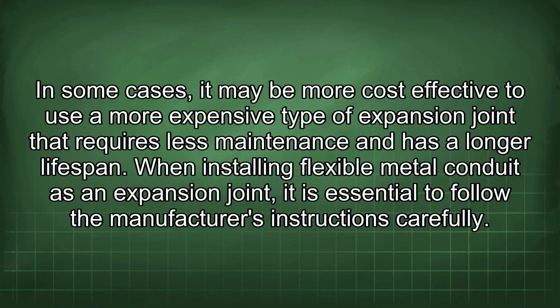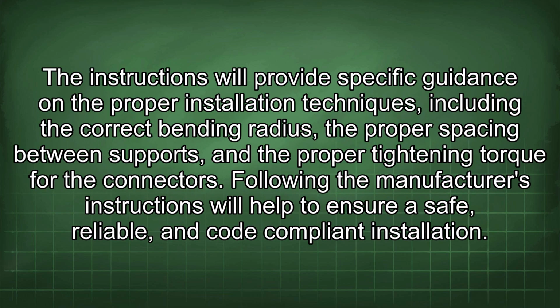When installing flexible metal conduit as an expansion joint, it is essential to follow the manufacturer's instructions carefully. The instructions will provide specific guidance on the proper installation techniques, including the correct bending radius, the proper spacing between supports, and the proper tightening torque for the connectors. Following the manufacturer's instructions will help to ensure a safe, reliable, and code-compliant installation.